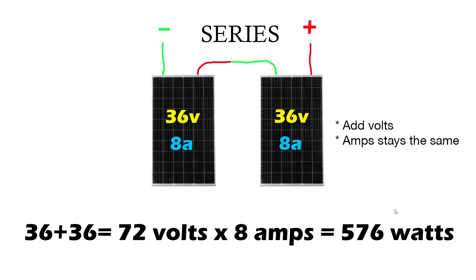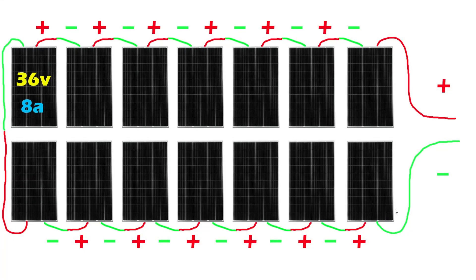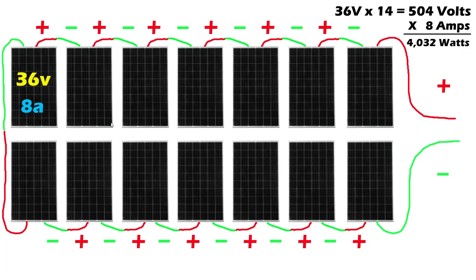The watts stayed the same but how we got there was different. What's very important when installing your own solar panel system is knowing what voltage and amperage your inverter can handle. From the previous video, I'm not supposed to exceed 550 volts, so I'm trying to get as close to that as possible without exceeding it. Here's an example of 14 solar panels in series — positive to negative, positive to negative — and if these are 36 volts at 8 amps each, we end up with 504 volts at 8 amps, which is 4,032 watts.